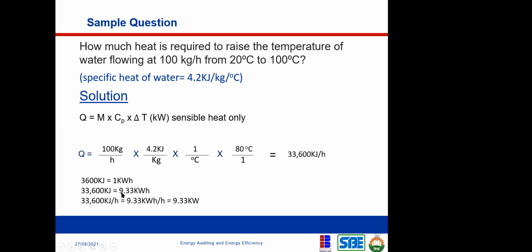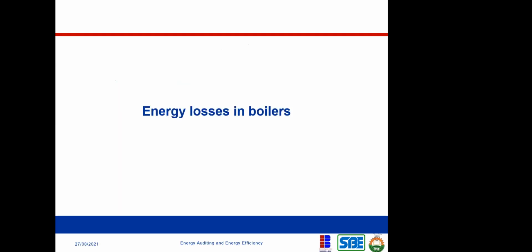Okay, so if we now check for 33,600 kilojoule, if you convert it to kilowatt hour, you're going to have 9.33 kilowatt hour, right? But you know that we still have per hour here, okay? So you have to divide it again by the hour, okay? Which is what we did here, 9.33 kilowatt hour per hour. So the hour will cancel the hour. You're left with 9.33 kilowatt, right? So that is the quantity of heat in terms of kilowatt that is required to raise this water from 20 degrees centigrade to 100 degrees centigrade. Any questions so far? I guess no. Okay, thank you.